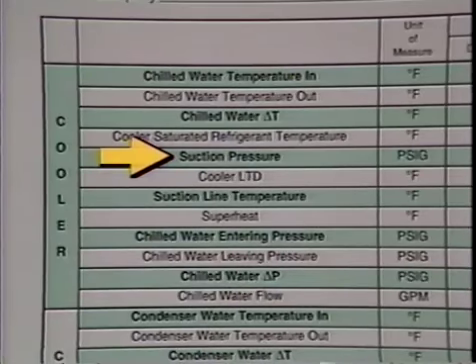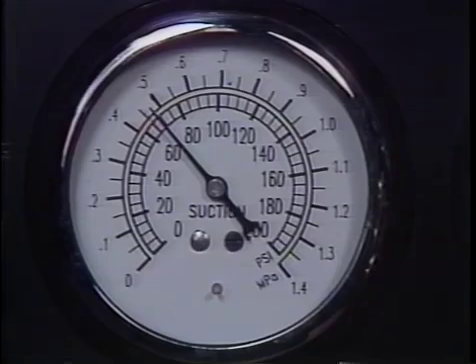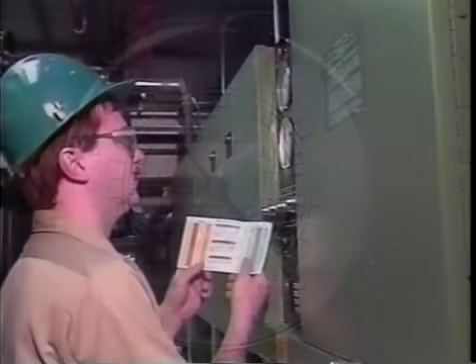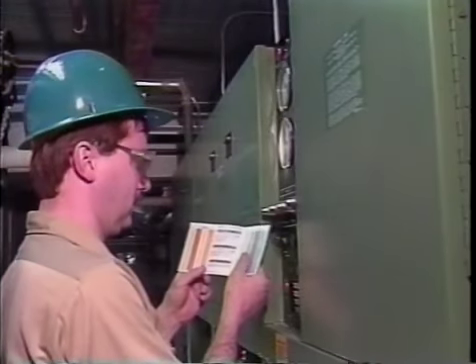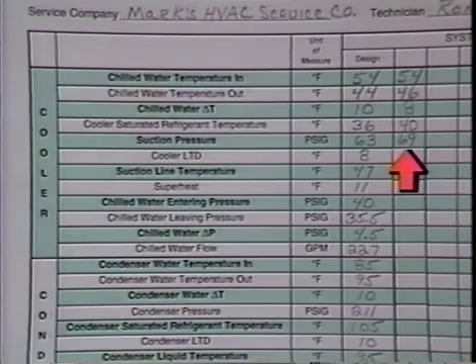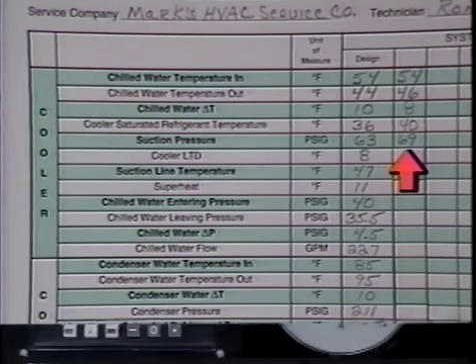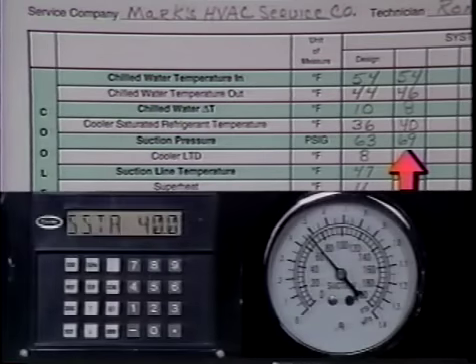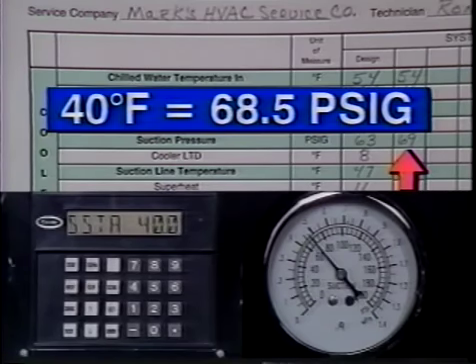Suction pressure. Read and record the suction pressure. Refer this pressure reading to a refrigerant pressure temperature chart. Compare its correlating saturated temperature to the actual cooler saturated refrigerant temperature reading. These two temperature readings should be the same or at least very close to each other.